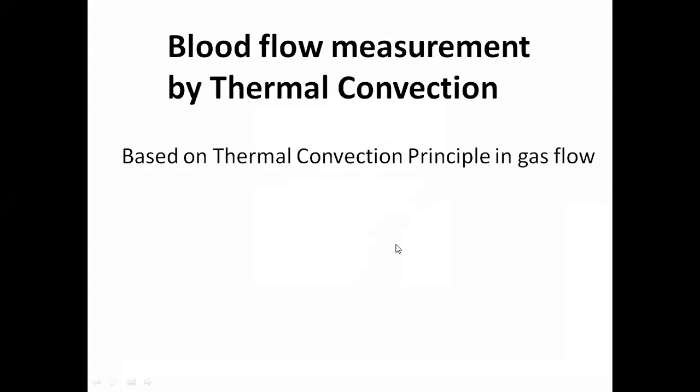When the blood is flowing through the heater, temperature variations occur, and those temperature variations are determined by the thermocouples. An electric heater is placed between two sensors.